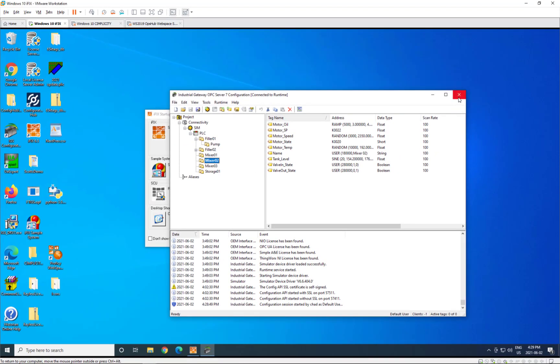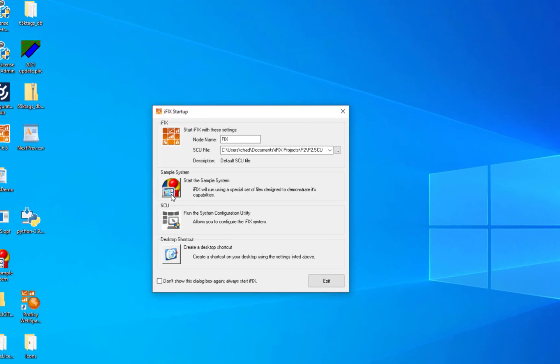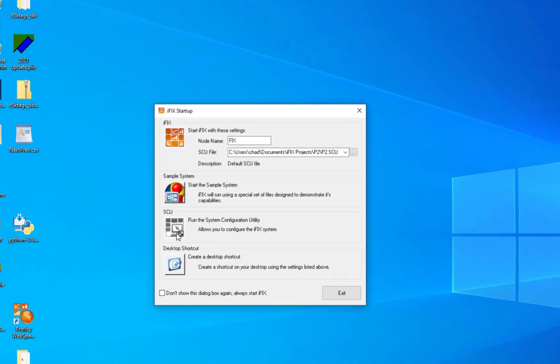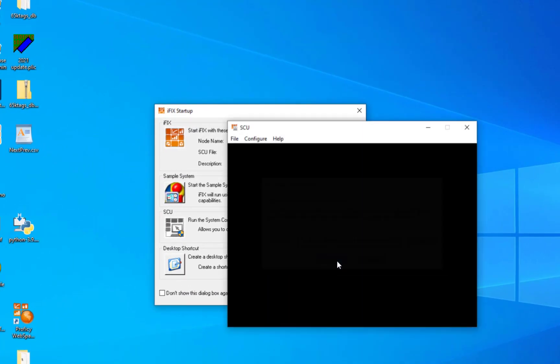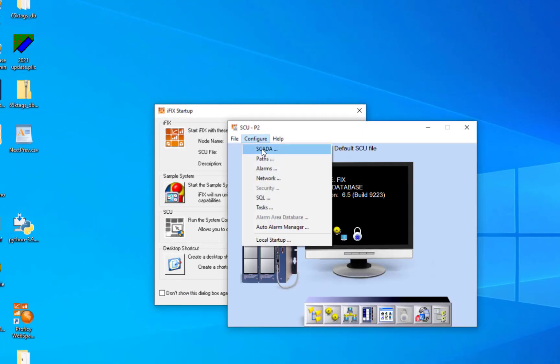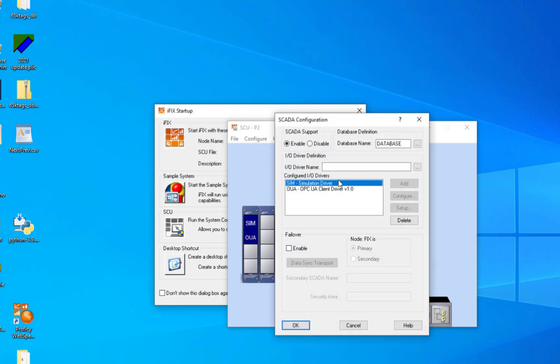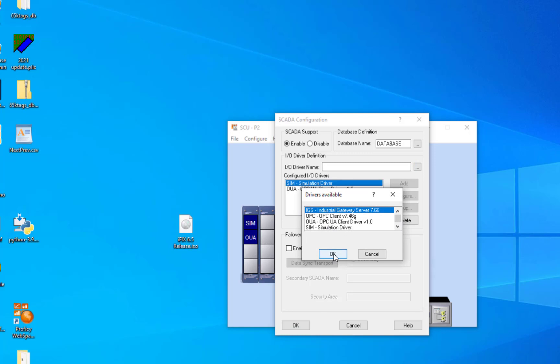So to get started, when you open your iFIX project, the first thing you'll need to do is go into your SCU, configure the SCADA, and add the IGS driver that is installed with iFIX when installing IGS on the same node as iFIX. You'll need to install IGS after iFIX so that that driver can be correctly installed.